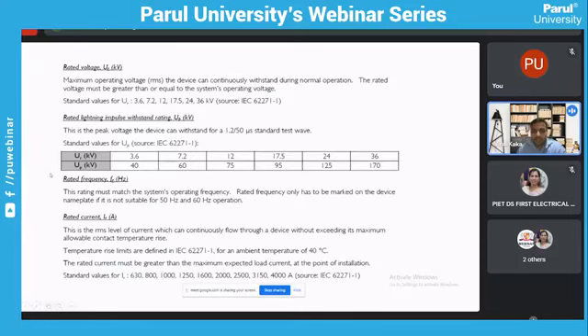Now, this is just an overview of the ratings of the switchgears offered in medium voltage switchgear. It's right from 3.6, 7.2, 12 kV, 17.5, which is followed for some of the EMEA region, 24 kV, and 36 kV as well. Again, these are all type tested at 50 as well as 60 hertz. So irrespective of the frequency variation, you can use your product in any country using 50 or 60 hertz. And the rated current, as I said previously, starts from 630, then 800, 1000, 1250, 1600, 2000, 2500, 3150, and 4000.